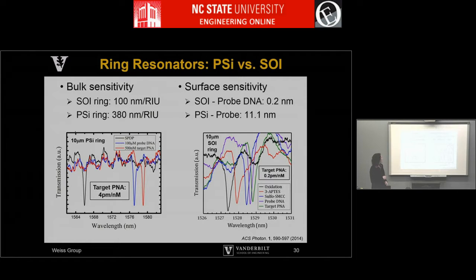So the silicon on insulator ring was about 100 nanometers per refractive index unit. The porous silicon ring is about a factor of 4 better. So that's for just volume infiltration of a solution. But where the surface area really shines is in terms of molecular attachment. So here you are very limited in your surface attachment to the SOI, the silicon on insulator, whereas for the porous silicon you access the volume.